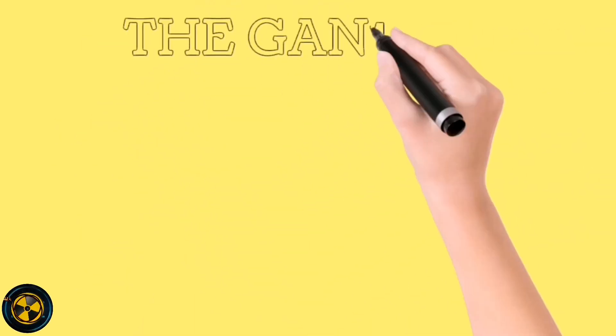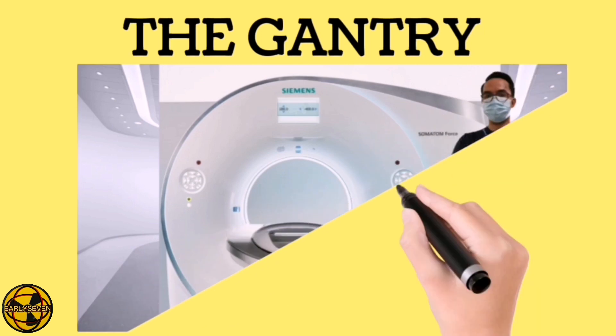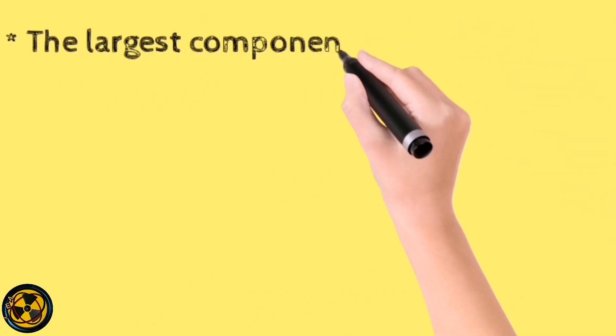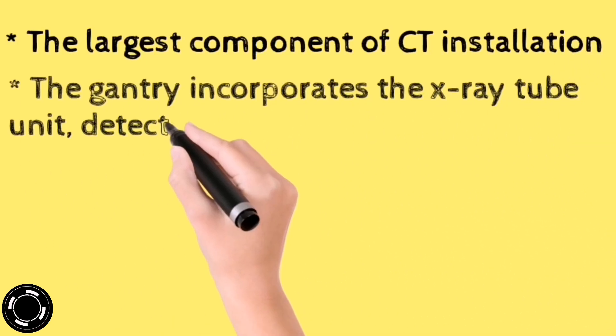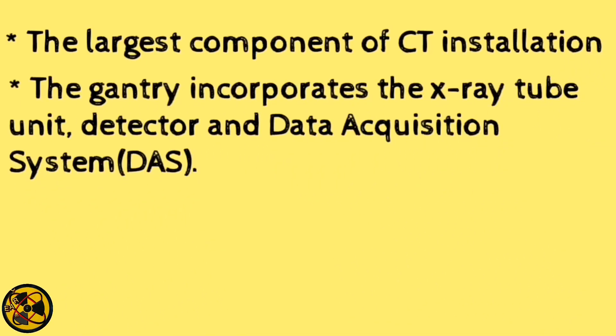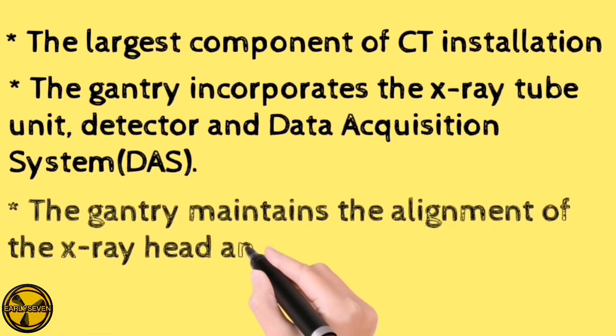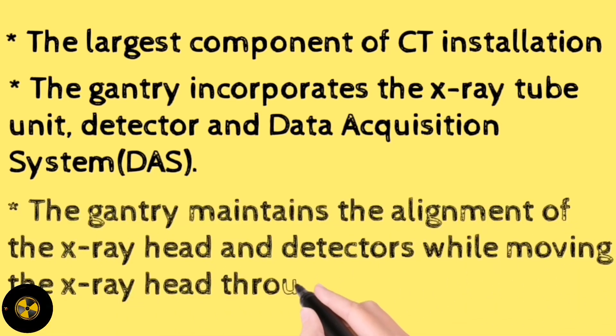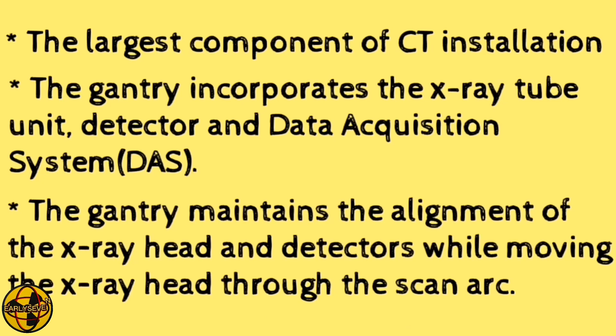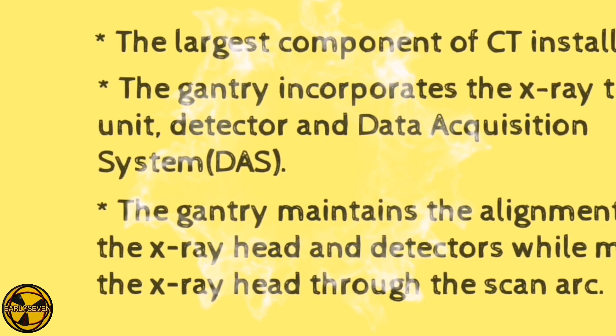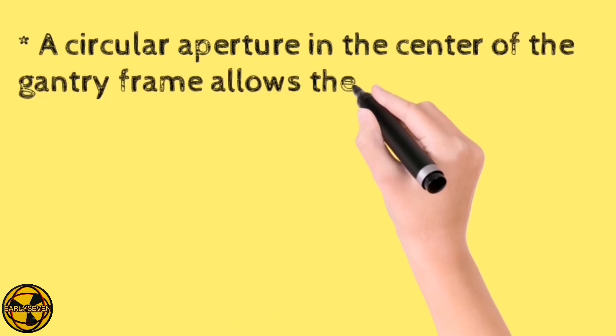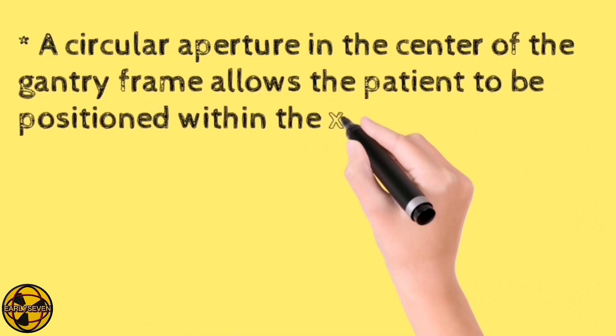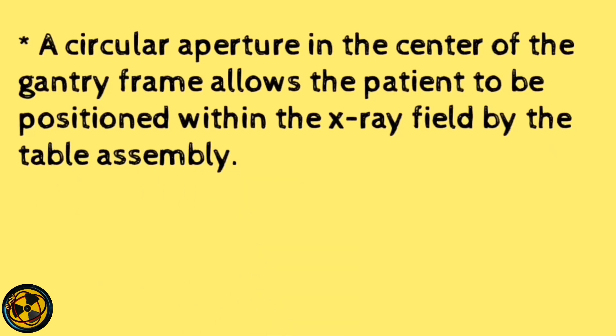Let us discuss the first component of a CT scanner which is the gantry. The gantry is the largest component of CT installation. The gantry incorporates the x-ray tube unit, detector and data acquisition system. The gantry maintains the alignment of the x-ray head and detectors while moving the x-ray head through the scan arc. A circular aperture in the center of the gantry frame allows the patient to be positioned within the x-ray field by the table assembly.